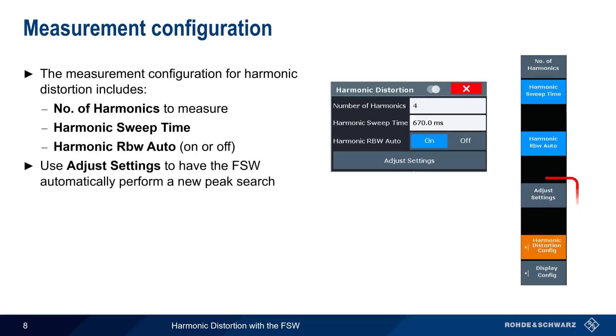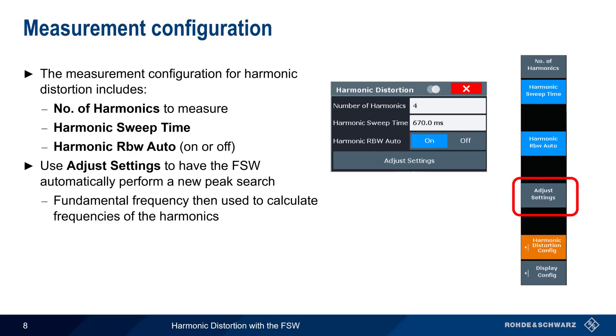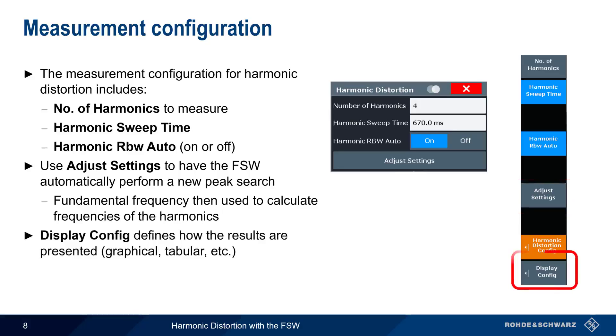Pressing the Adjust Settings button causes the FSW to automatically search for the peak — that is, the fundamental. The FSW will then use this frequency to calculate the frequencies of the harmonics. As with most FSW measurements, the Display Config button can be used to select how the measurement results are displayed — that is, in a trace, in a table, etc.